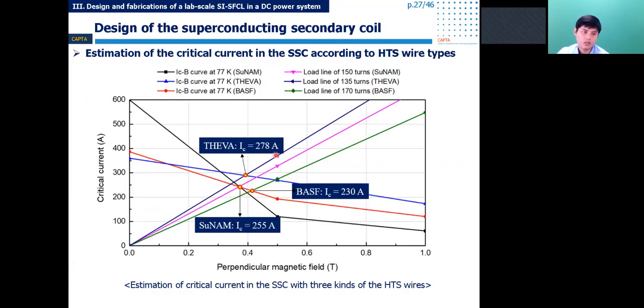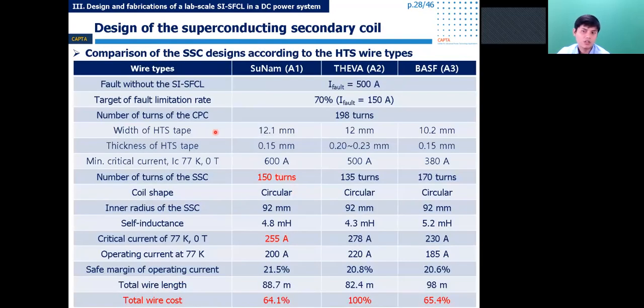So next is the design of the secondary superconducting coil. Three HTS wire types with different properties and costs were considered, including SuNam, THEVA, and BASF, with the same targets of fault limitation of 70%, a safety margin of 20%, and an operating temperature of 77 Kelvin. The coil design, the number of turns, and the critical current were determined in this graph. The summary and the comparison of the secondary coil with the 3 kinds of HTS wire is shown in this table, with the same design targets of the SFCL. Considering the wire cost, the SuNam wire is the most suitable, and I selected it for the secondary coil fabrication.